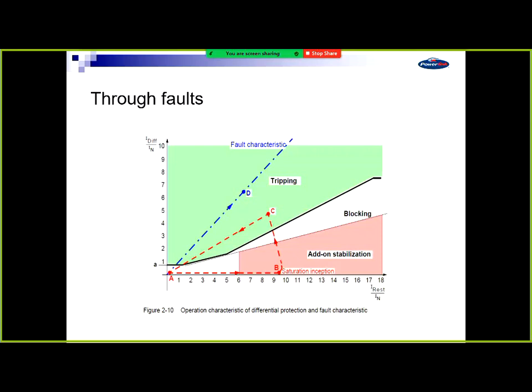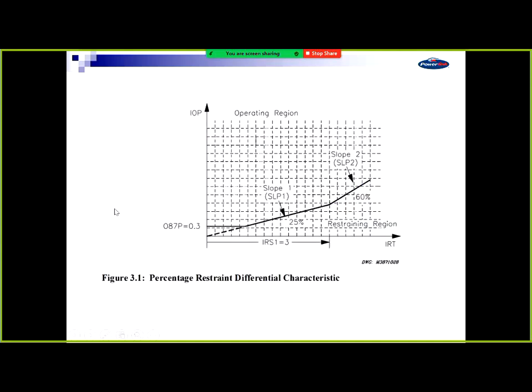Our CTs will saturate in 40 milliseconds then. You send out your trip signal in about 20 or 25 milliseconds. If you've got that much fault current, you're going to be above that pickup that I mentioned, that top one, and you'll be sending your trip signal out in 20 milliseconds. So the decision is already made for you. If it saturates, if it happens to be external, you actually don't get all of that current flowing through because it's got multiple ways it's going. But if it did saturate, 40 milliseconds is enough time for a modern relay, that we buy, to be able to determine that it's a saturated CT. It's actually a lot more. Probably what they're specifying or telling you that you need would saturate in 5 or 10 milliseconds. So we're still very conservative.